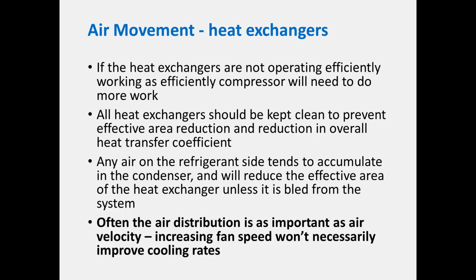Now, if air gets into your refrigerant system, it tends to accumulate in the condenser because that's often the highest point. If you have air at the top of your condenser, it's removing a certain amount of area that could be used for condensing your liquid, reducing its effective area. So periodically it may need to be bled.